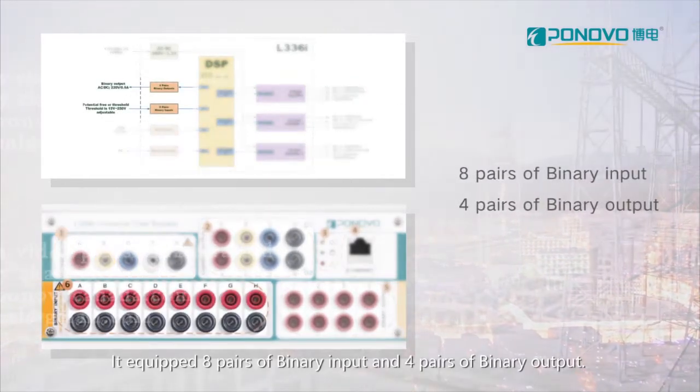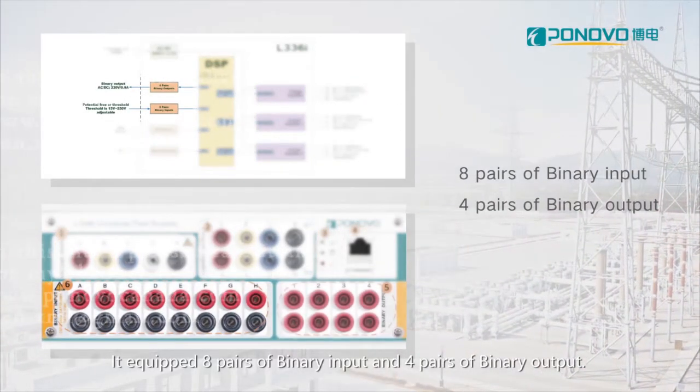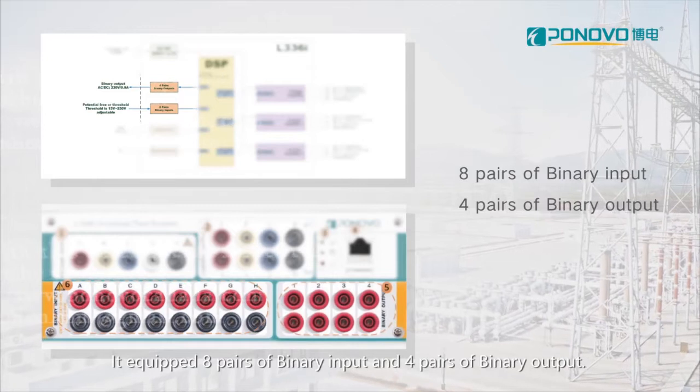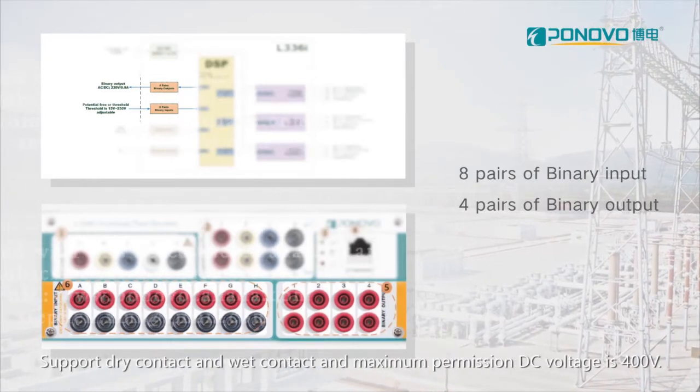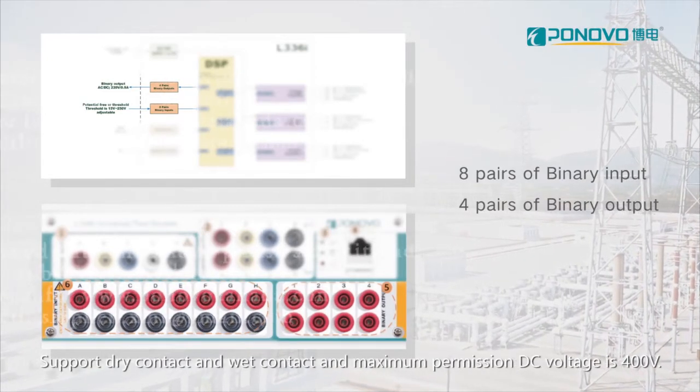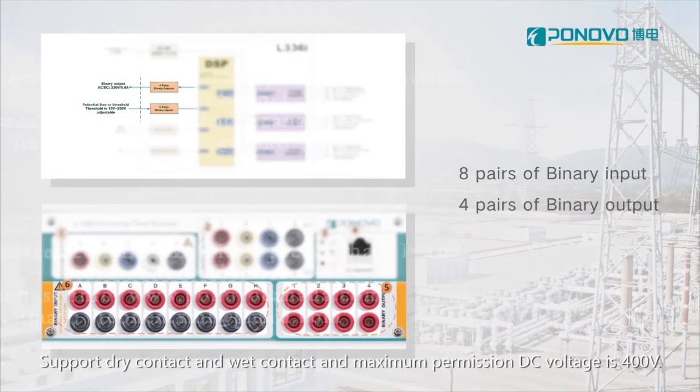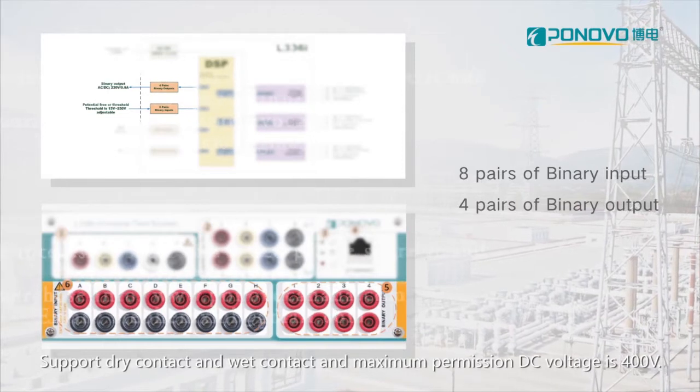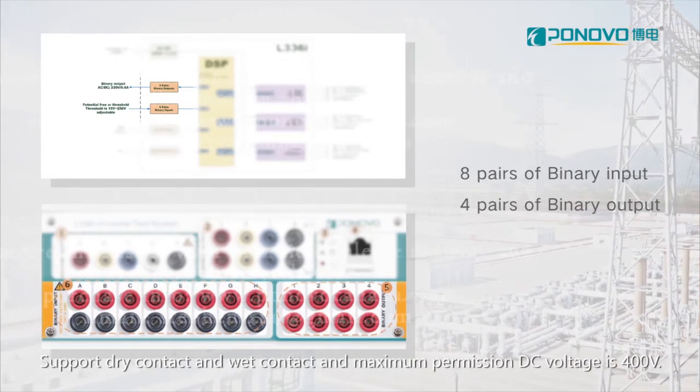It equipped eight pairs of binary input and four pairs of binary output. Support dry contact and wet contact and maximum permission DC voltage is 400 volts.